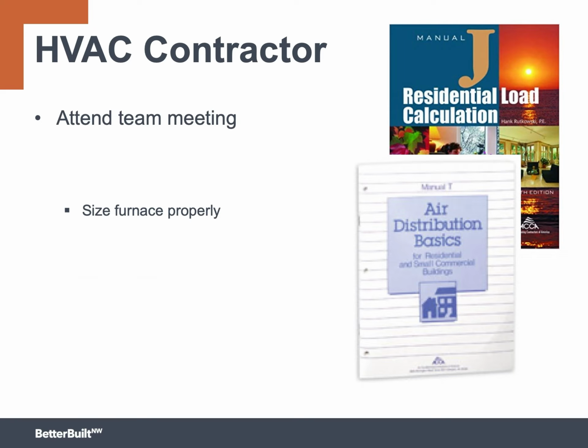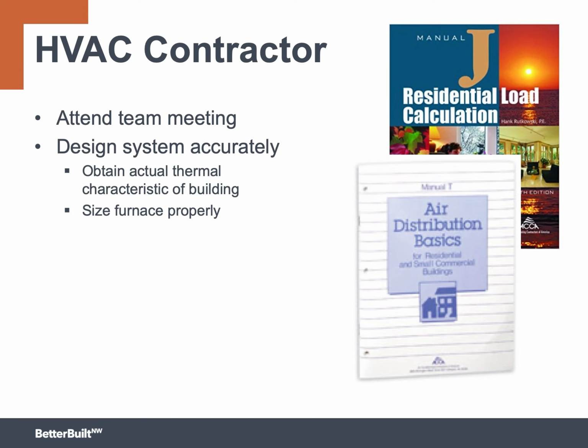The intuition and rules of thumb that HVAC contractors have developed working with typical construction simply don't apply to ducts inside. They need to revisit those assumptions by actually doing a full set of calculations on the building. Once they've gone through this process of calculating the heating and cooling needs of a particular house, or maybe several houses, or maybe a dozen houses, it's possible they'll develop a new intuition that is appropriate for this new approach. But in the meantime, they'll need to pay close attention to the actual thermal characteristics of the building when they do a Manual J calculation.